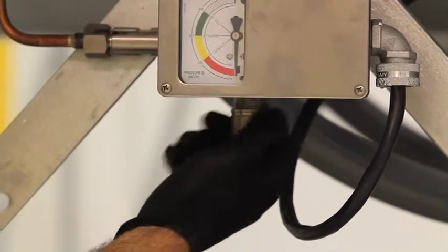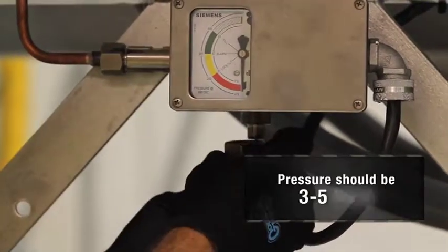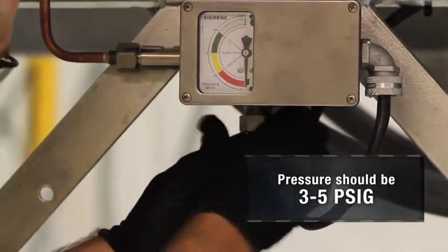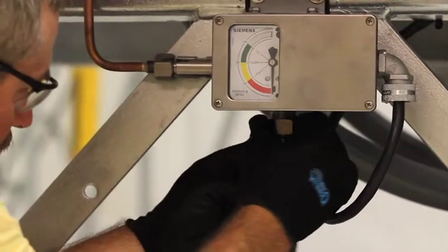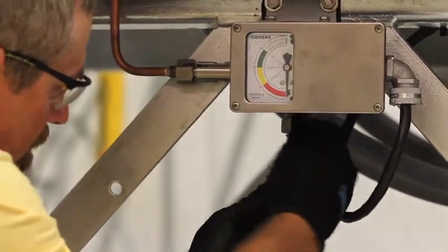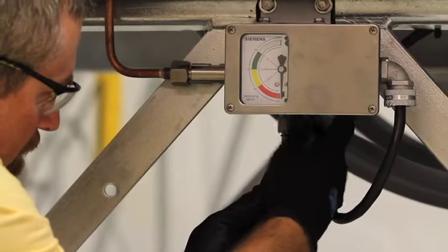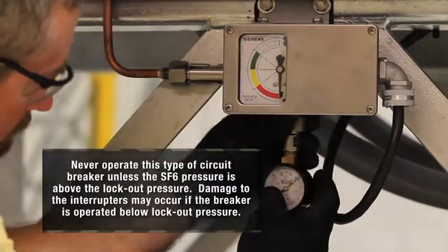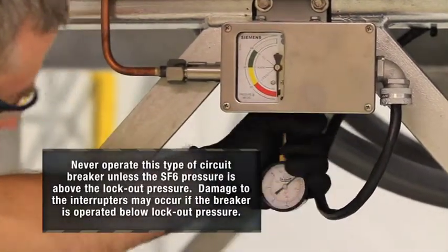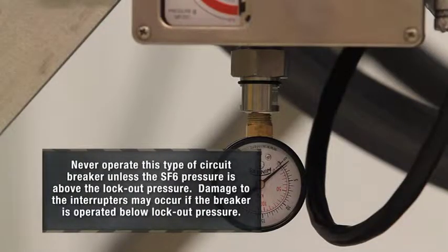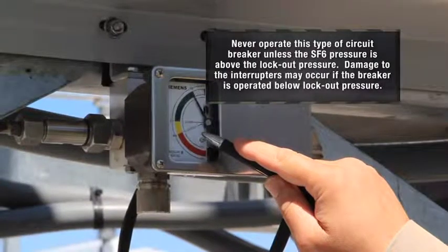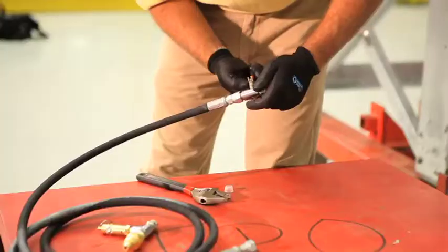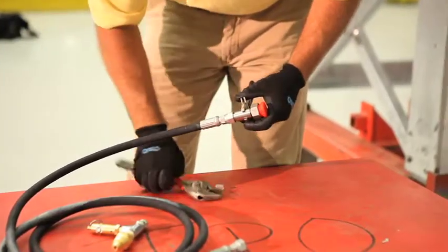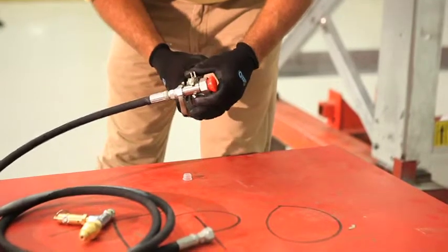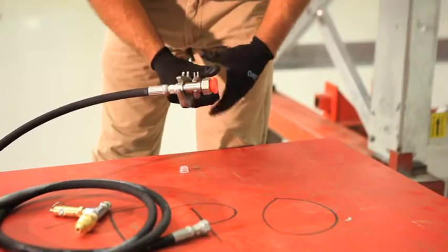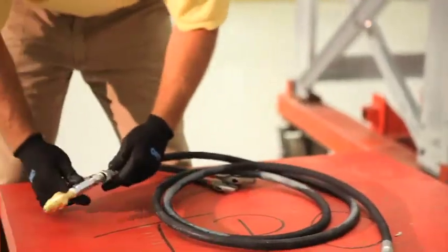Each breaker is shipped with a positive pressure of approximately 3 to 5 psig of SF6. The outside density gauge does not resolve to this level, so in order to verify, attach the small pressure gauge that is shipped with the breaker to the outside density gauge fill port. If for some reason it is less than 3 psig, please contact your Siemens representative. Use the hose and fittings shipped with the breaker to connect to the SF6 cylinder. Attach the quick disconnect fitting, then securely connect the relief valve manifold assembly.